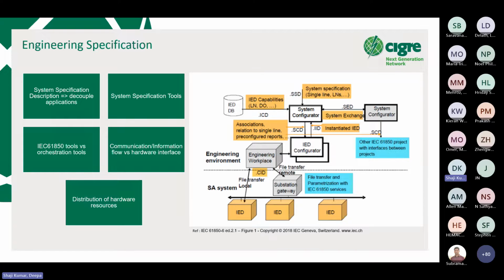Each IED requires a subset of system configuration information, provided by the device-specific configured IED description, or CID file, derived from the SCD file using the IED configuration tool. To allow local modifications at the IED level and the necessary update of the SCD file, we have instantiated IED description files, created by the ICT tools and uploaded onto the SCT. So we can have either a bottom-up or top-down approach for engineering and specification.